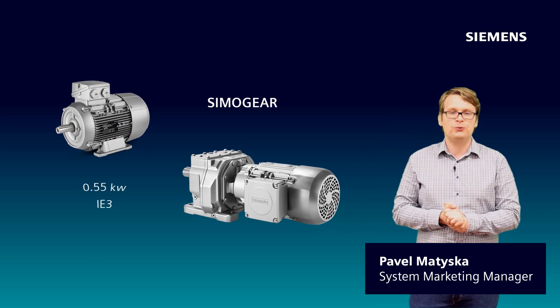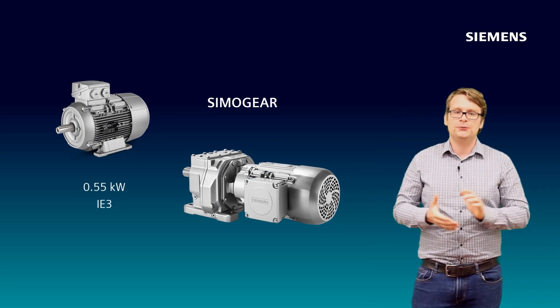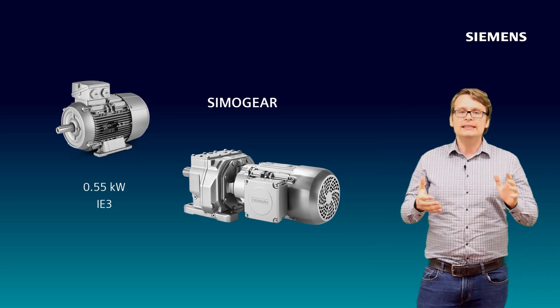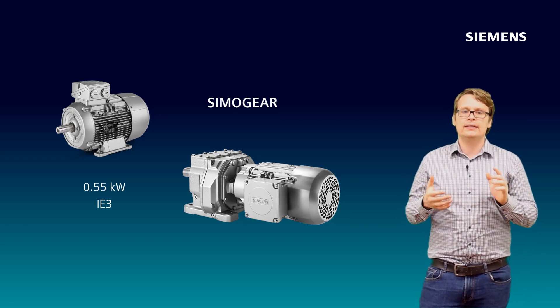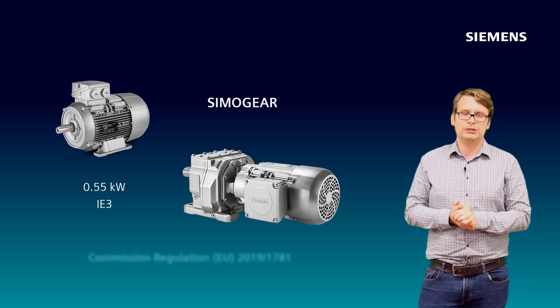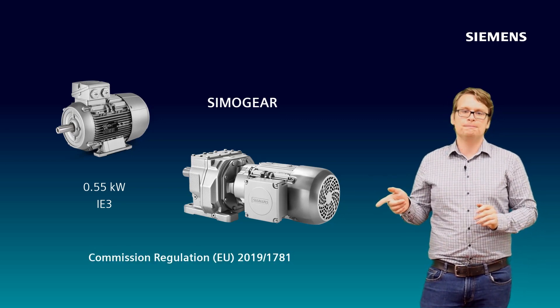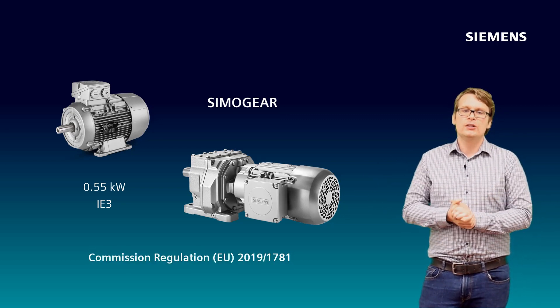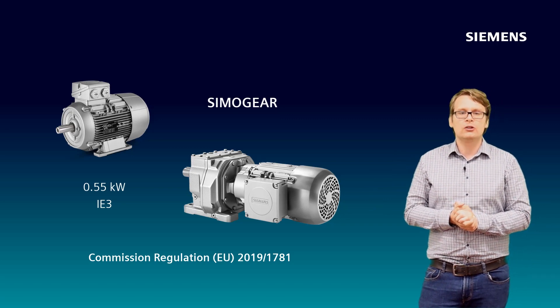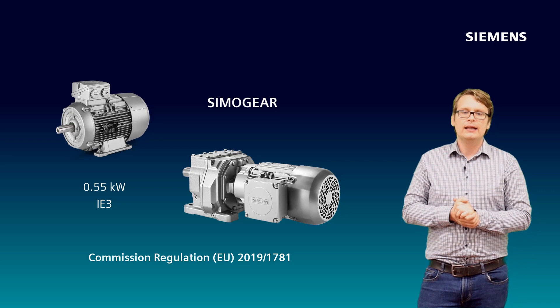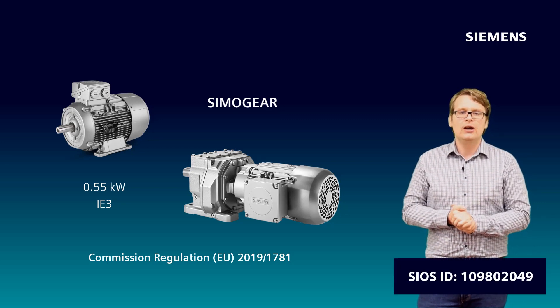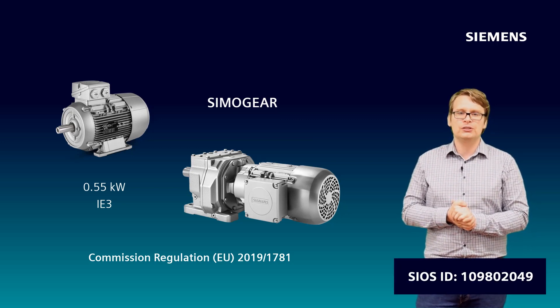The SIMOGEAR portfolio has been extended with 0.55 kW motors in IE3 efficiency class. This IE3 efficiency for 0.55 kW motors exceeds the requirements from the EU mentioned here. It is required from July 2021 that all motors from 0.75 kW must fulfill IE3 also in converter operation.